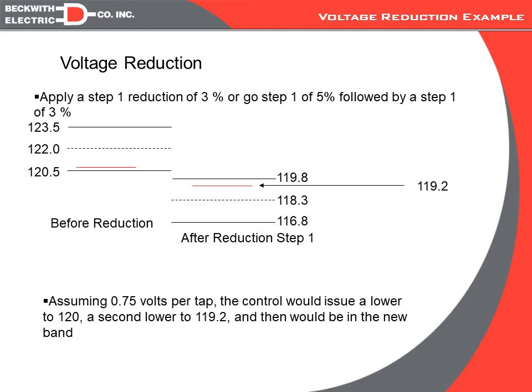Now, taking the same example, but changing it to a 3% reduction instead of 2%, we calculate a new band of 118.3, still using our same 3-volt bandwidth. We can see that there's no overlap. So the high band is below the old low band. This guarantees that no matter what the voltage was prior, we will definitely be forced to take a lower to get into the new band.